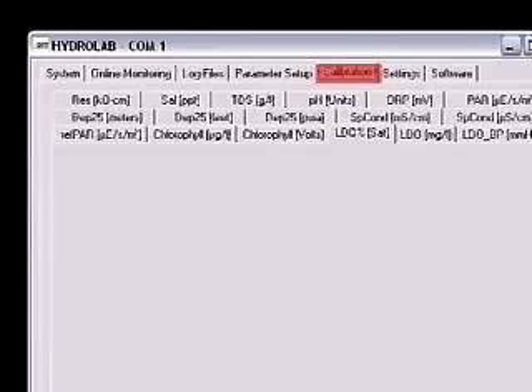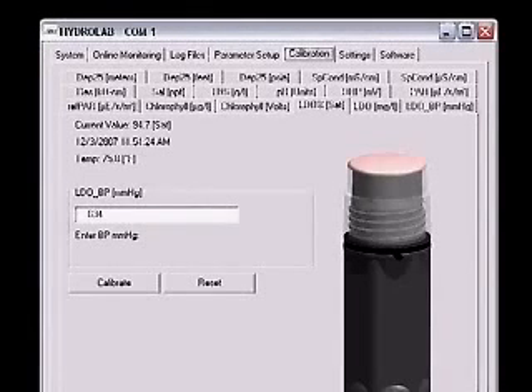When the sonde is ready to operate, click the Calibration tab. Select LDO %SAT tab. A picture of the LDO sensor should appear on the screen. Wait for the current value and temperature readings to stabilize. If the cap was stored wet, this should happen very quickly. A dry cap may take several minutes to stabilize.